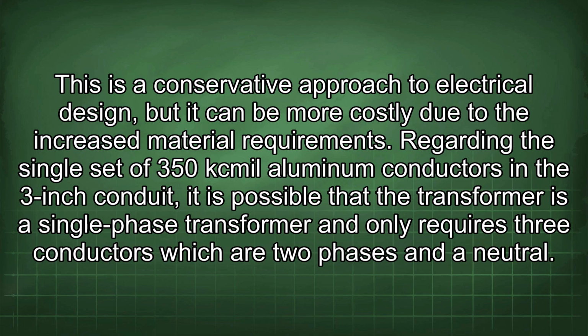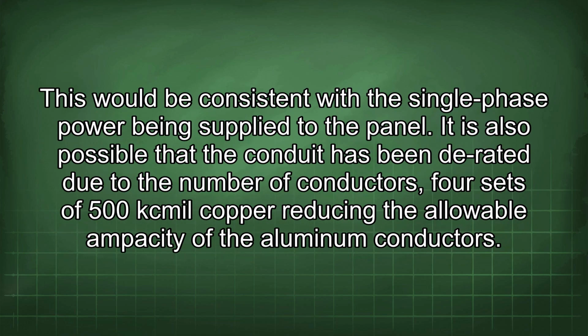Regarding the single set of 350 kcmil aluminum conductors in the 3-inch conduit, it is possible that the transformer is a single-phase transformer and only requires 3 conductors, which are 2 phases and a neutral. This would be consistent with the single-phase power being supplied to the panel. It is also possible that the conduit has been derated due to the number of conductors, 4 sets of 500 kcmil copper, reducing the allowable ampacity of the aluminum conductors.